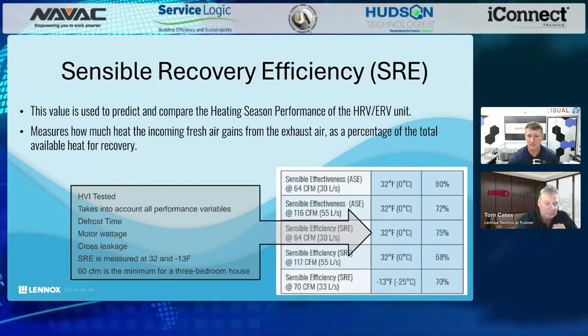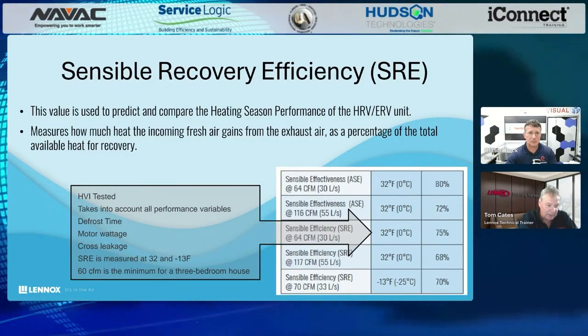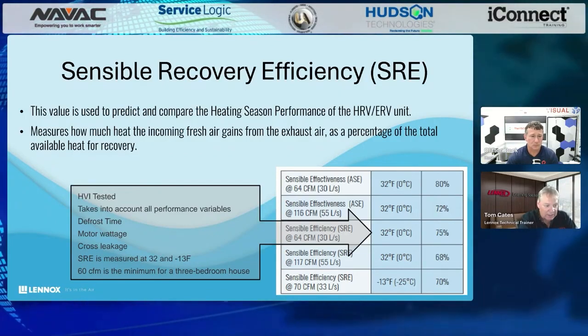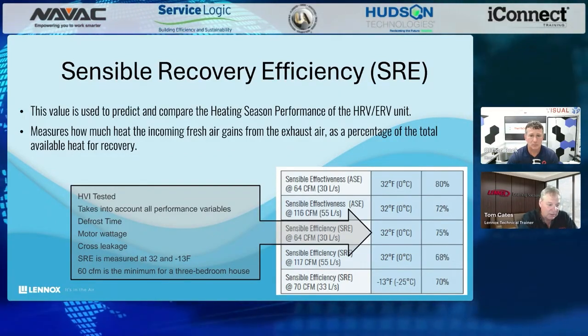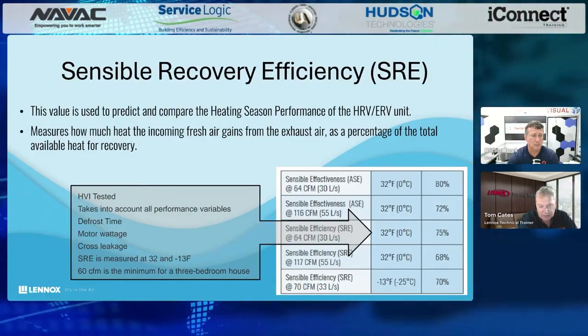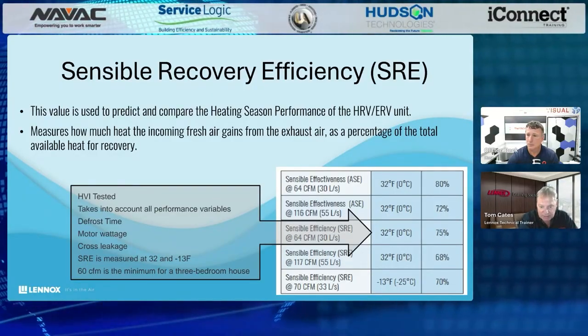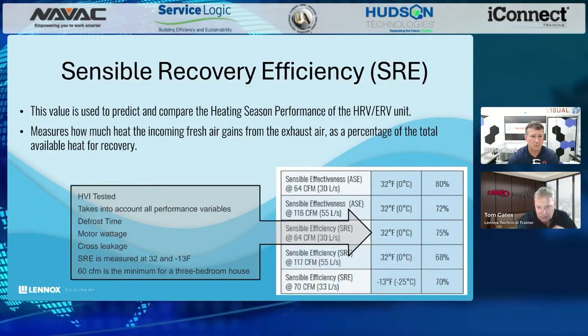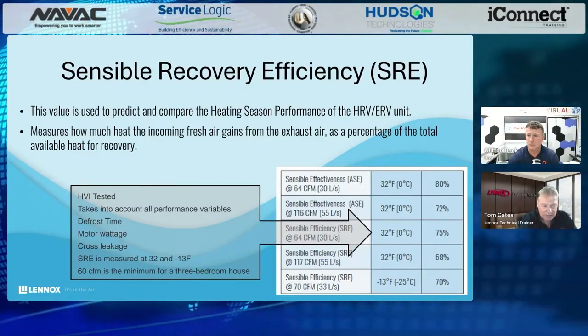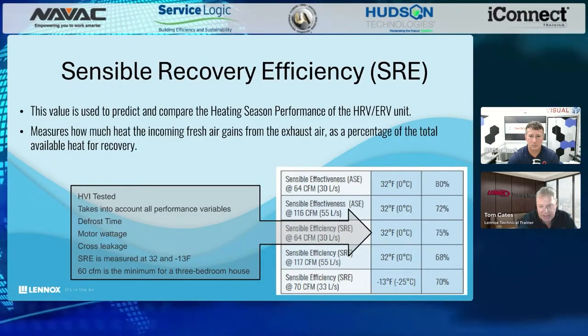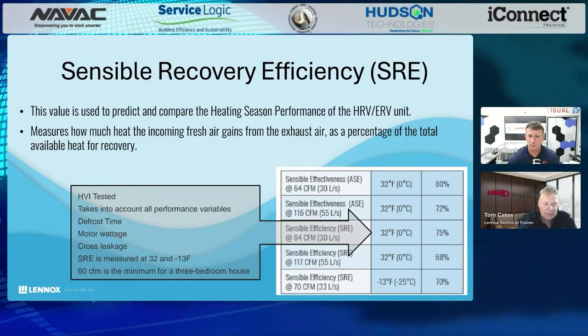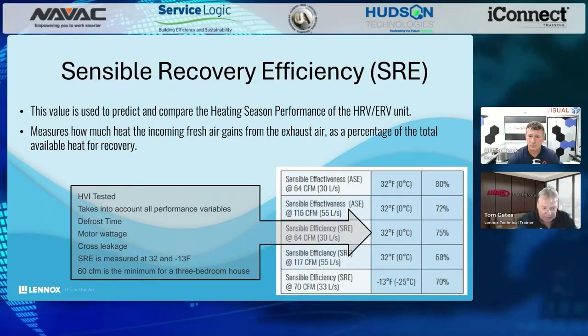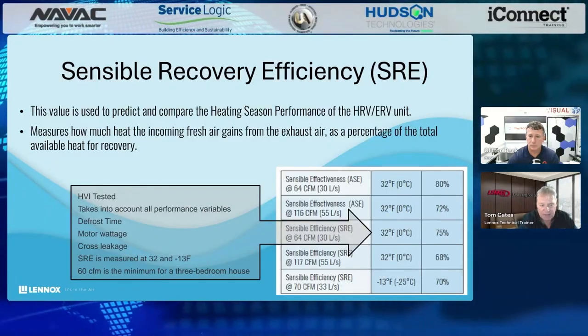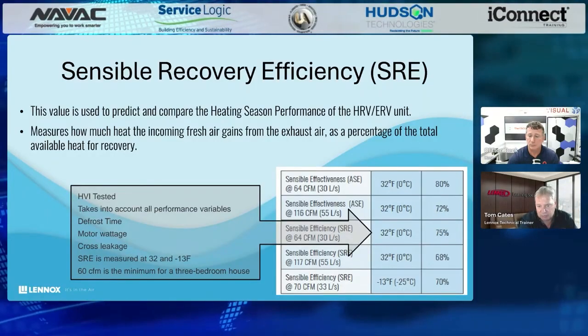It takes into account things like defrost time, motor wattage, and cross leakage of the core. It's typically measured at two conditions: 32 degrees Fahrenheit and minus 13 degrees Fahrenheit, for different climate zones where you might be installing this equipment. It's generally looked at a CFM of 60 CFM. If I change the delivery rate of the air, the amount of CFM, it changes the sensible recovery efficiency, but it kind of goes along with that.